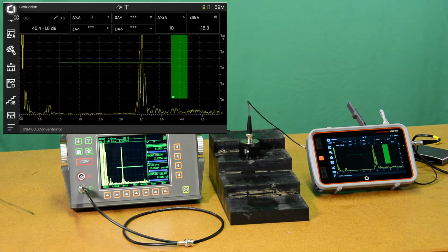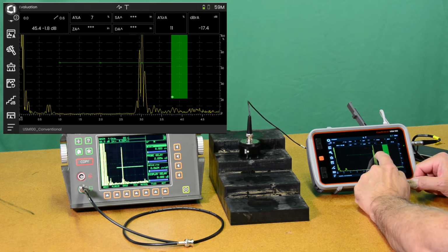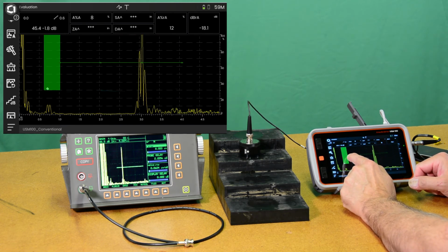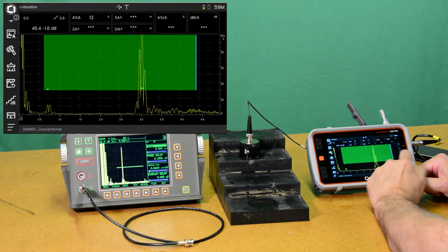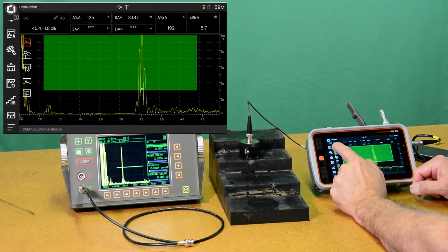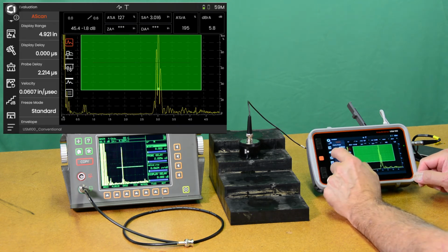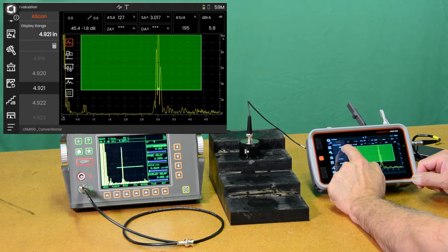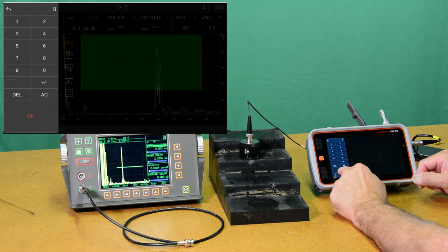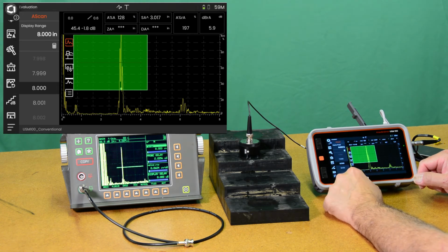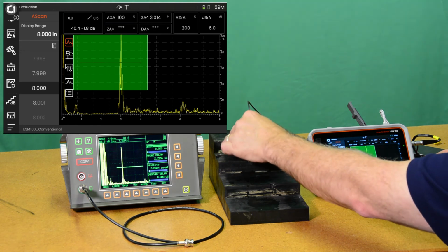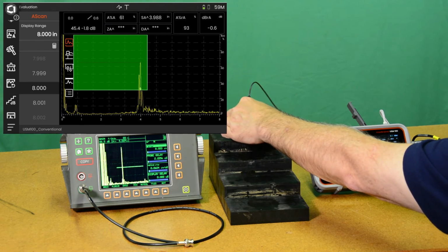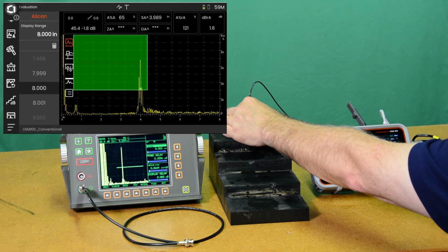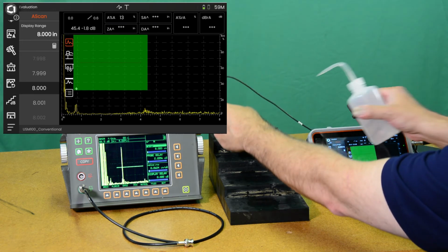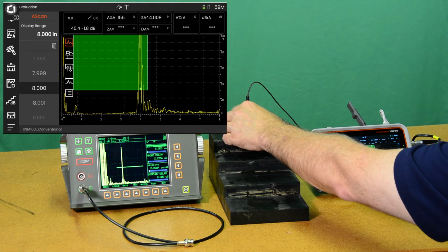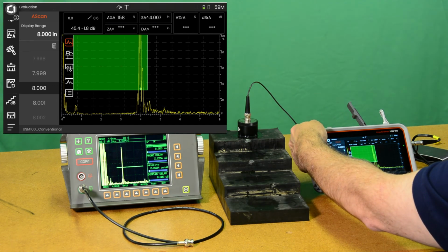So now we have a setup that allows us to take, if I widen my gate here, it's by touching and dragging on the screen. Maybe I want to go to a wider A scan. I think we had 8 inches on our USM 60, so let's set that up the same. Okay, so there's 8 inches. We're at half screen. Go to the 4-inch step. There's my, give it just a little bit more couplant. There we go. Take a little gain out.